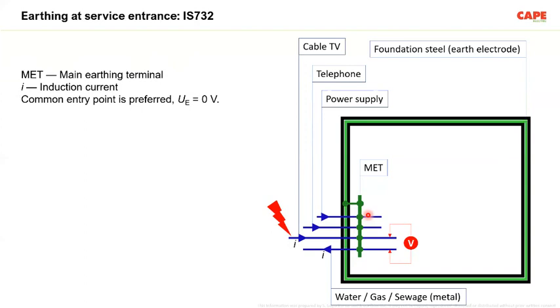Purpose number 1 is reducing the shock voltage of simultaneously accessible metallic parts inside the building. Number 2, in case of any lightning overvoltage coming through a particular line, the overvoltages are limited to a minimum. And number 3, which is very important: whenever there is a fault on the high voltage side of the distribution transformer, and the network is a TNCS or a TNS network, the shock voltage inside the consumer premise due to the high voltage fault is also minimized because of this protective equipotential bonding.